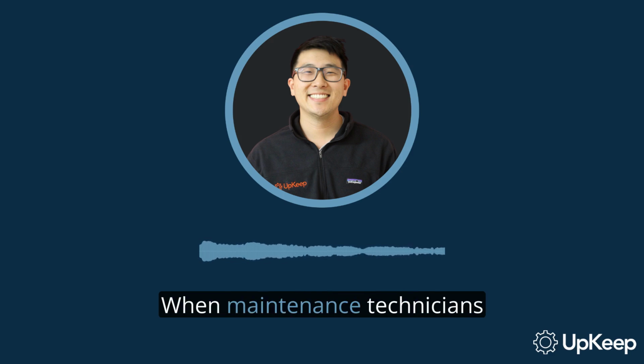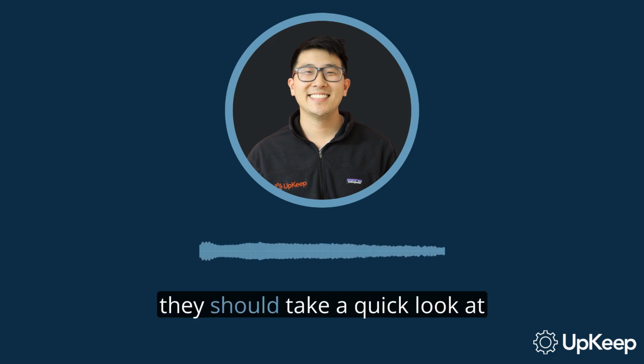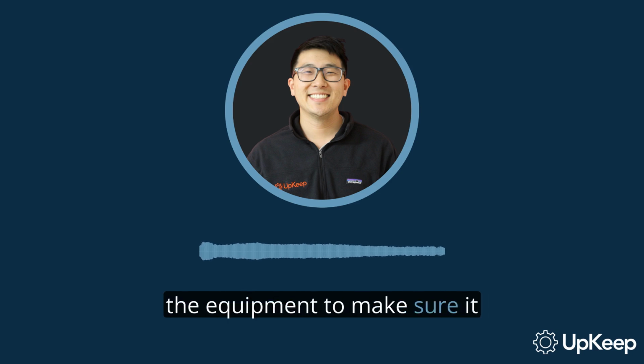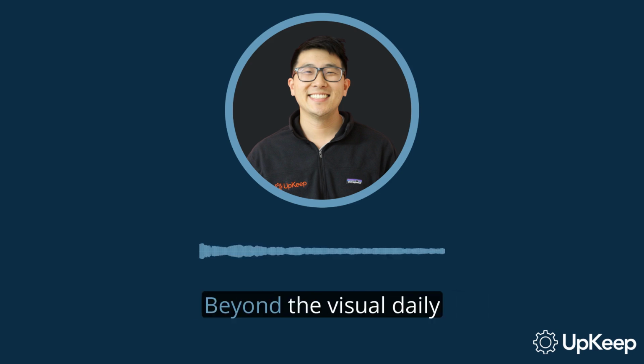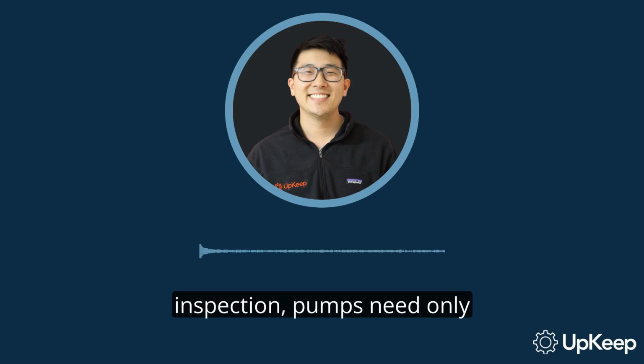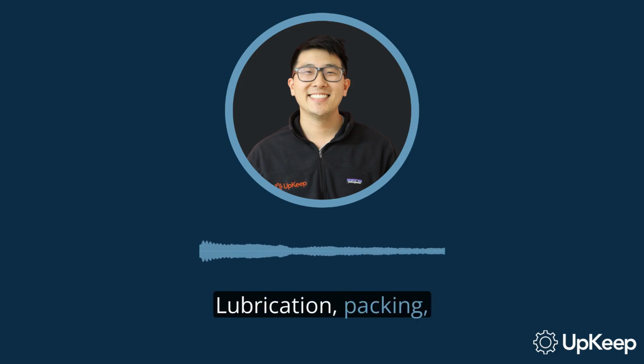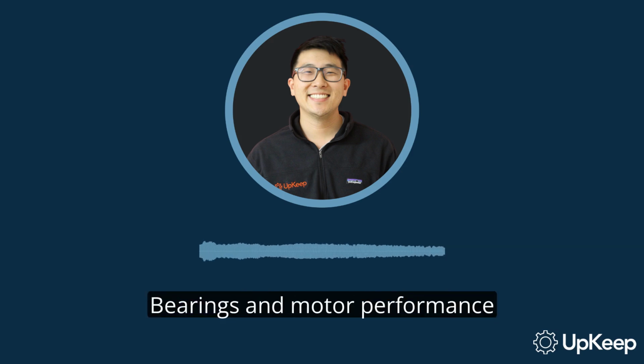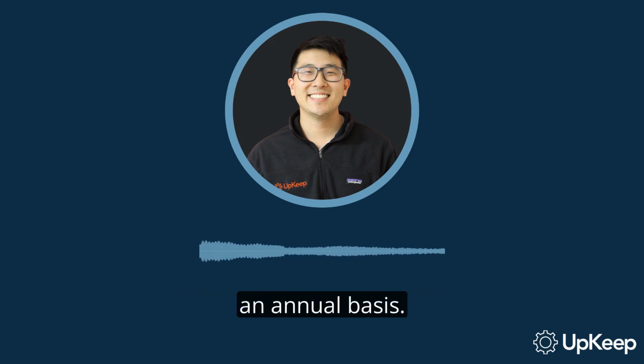on time. When maintenance technicians service a pump, they should take a quick look at the equipment to make sure it appears to be operating properly. Beyond the visual daily inspection, pumps need only monthly and annual maintenance. Lubrication, packing, alignment, and mounting should be checked every month. Any problem should be resolved immediately for peak performance. Bearings and motor performance should be inspected on an annual basis.